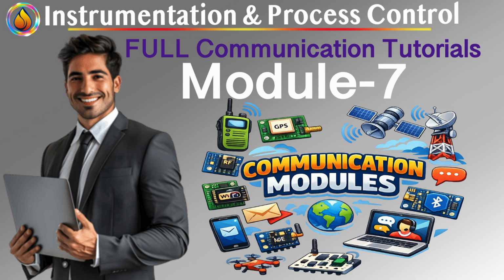LAS, the quiet authority on the bus. Now let's talk about the heart of the system. The Link Active Scheduler, LAS, is not a device type. It is a role assumed by one link master at a time. The LAS is responsible for maintaining network time, enforcing the communication schedule, and issuing compel data commands. Think of the LAS as the conductor. No musician decides when to play; the conductor does.